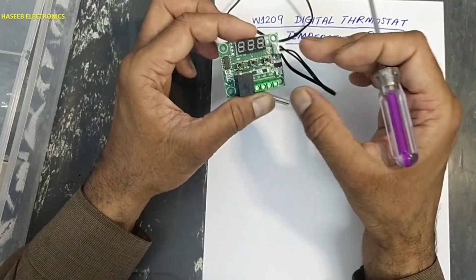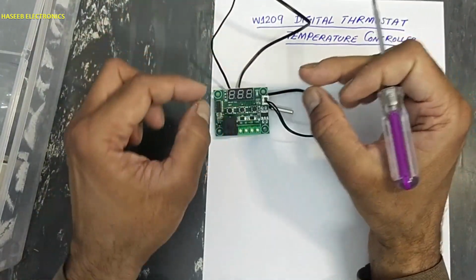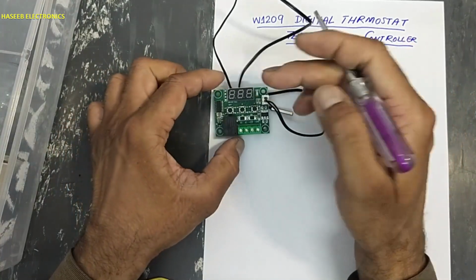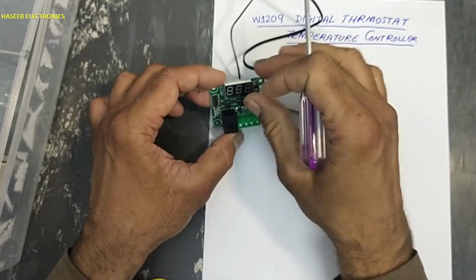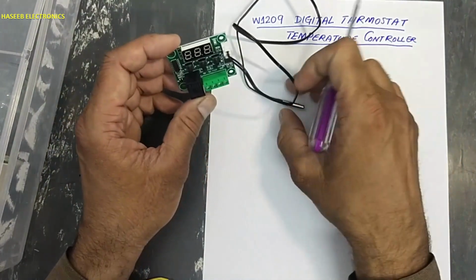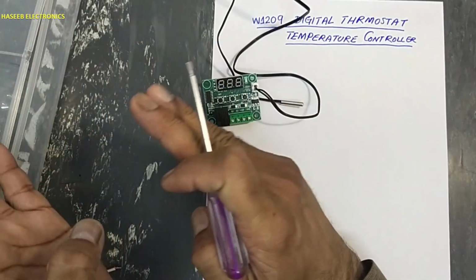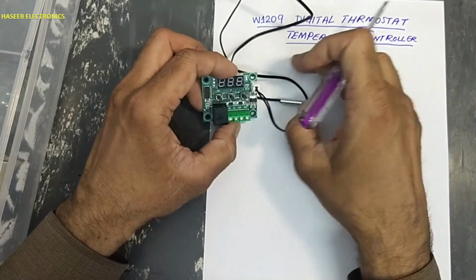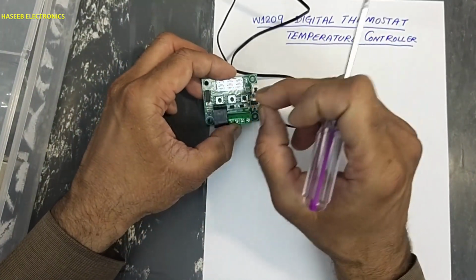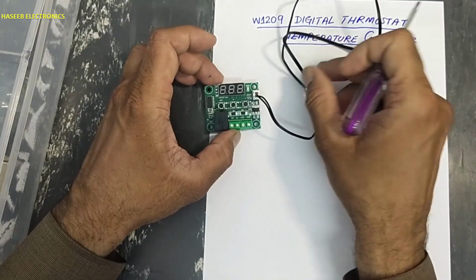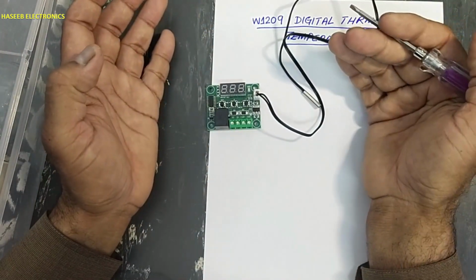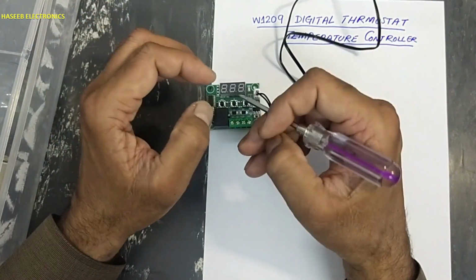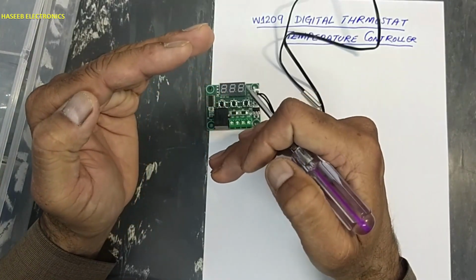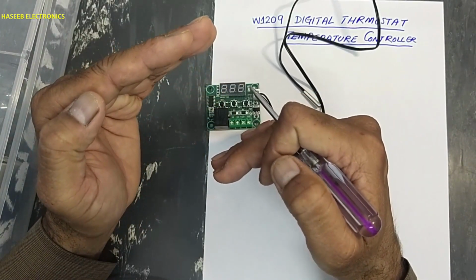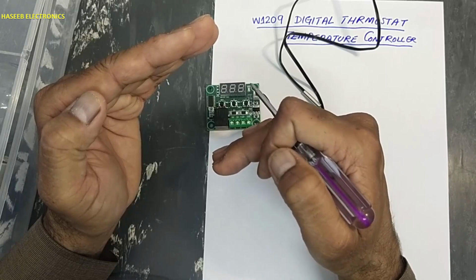When the temperature reaches a certain limit that is adjusted from this control panel, it will turn on the load. We can use it for heat mode or cool mode. When we are using it in heat operation, it will control the temperature and the power of any heater.